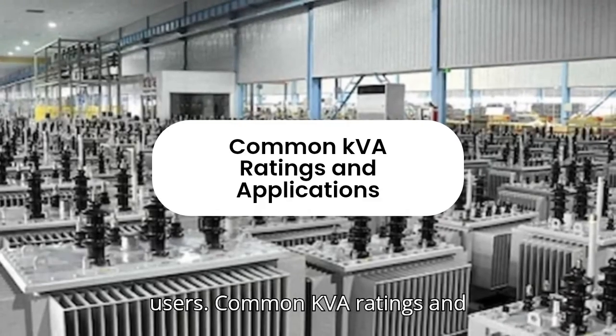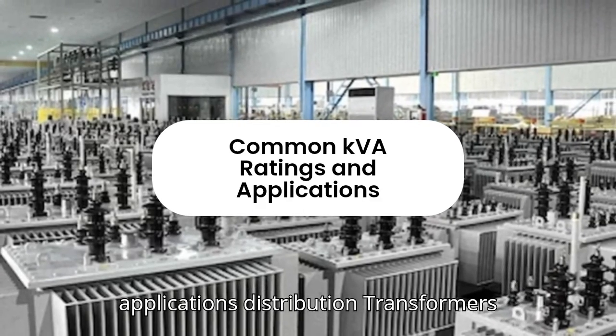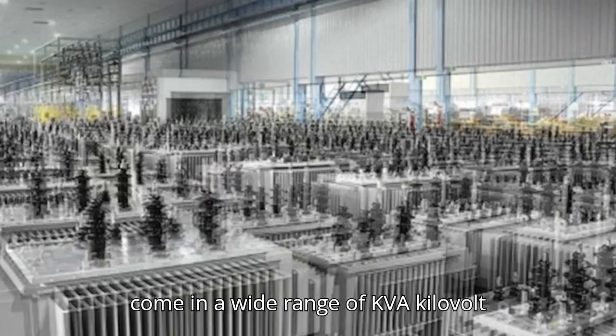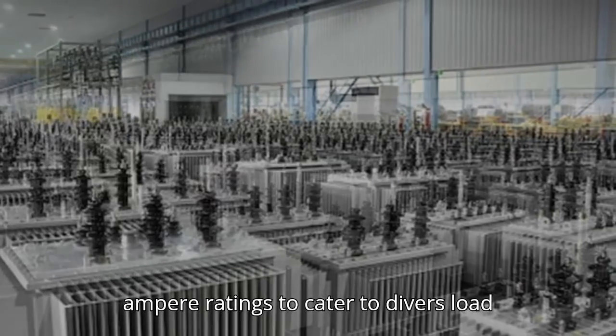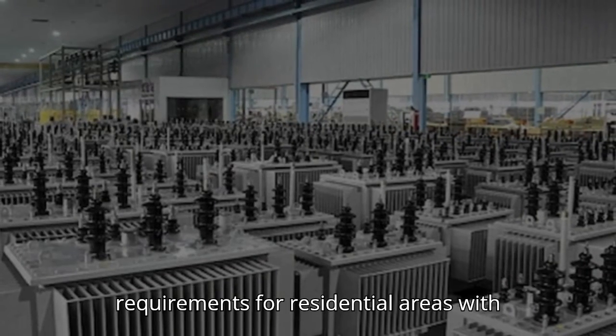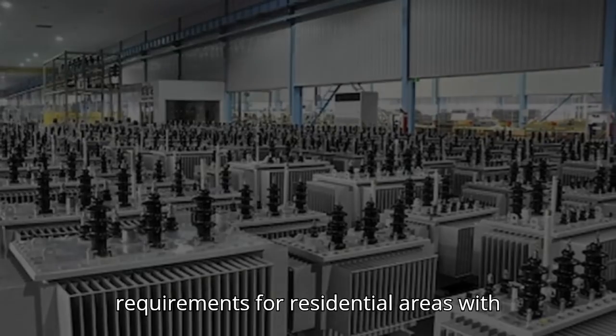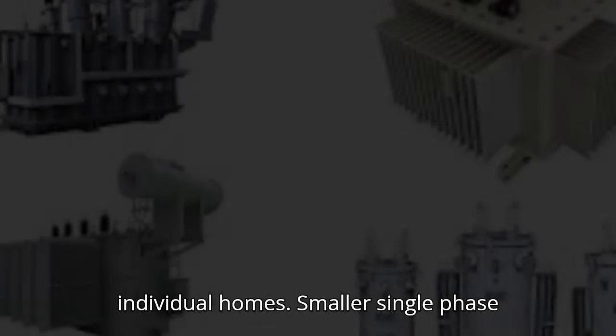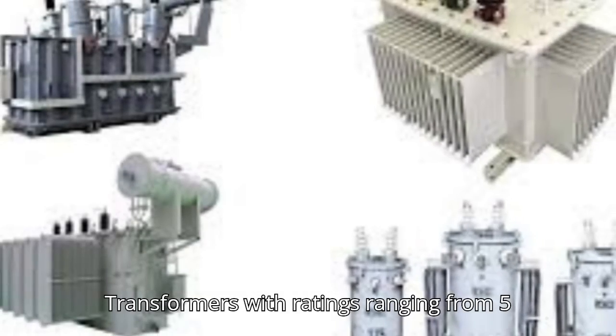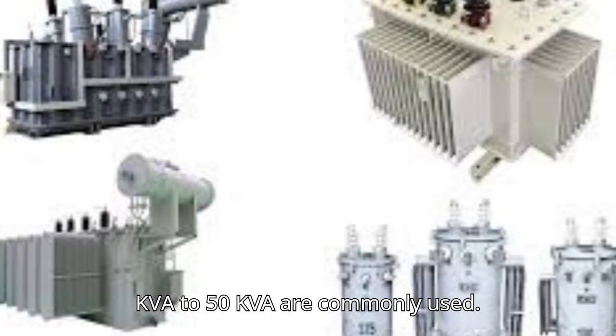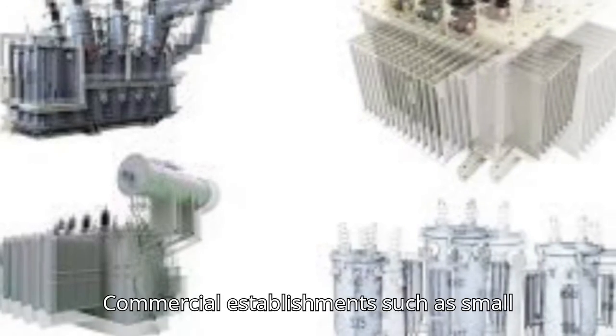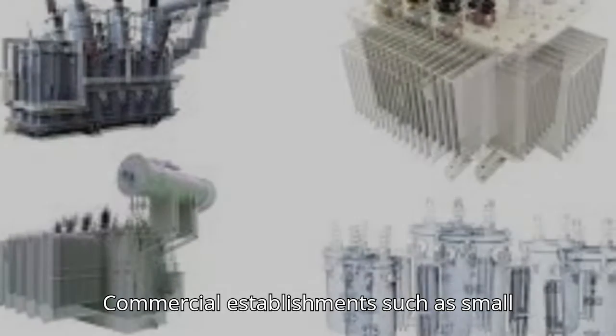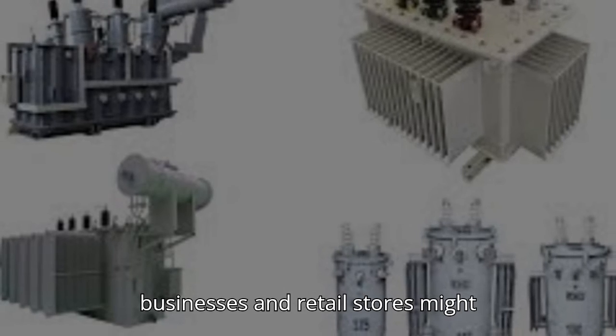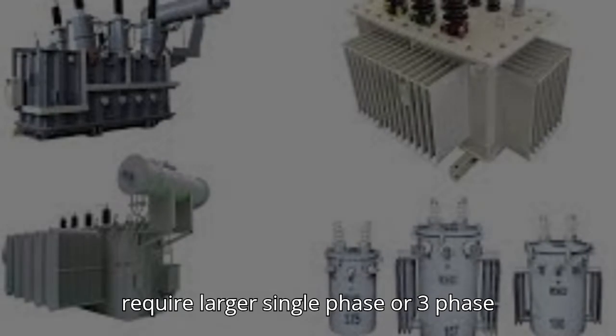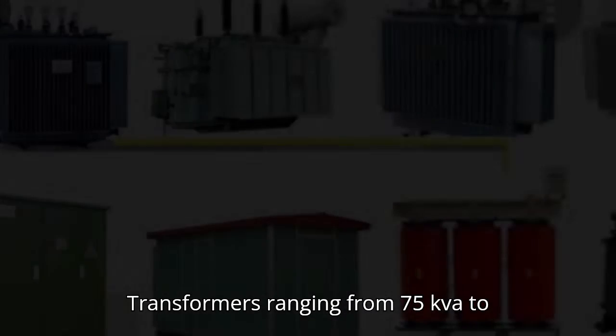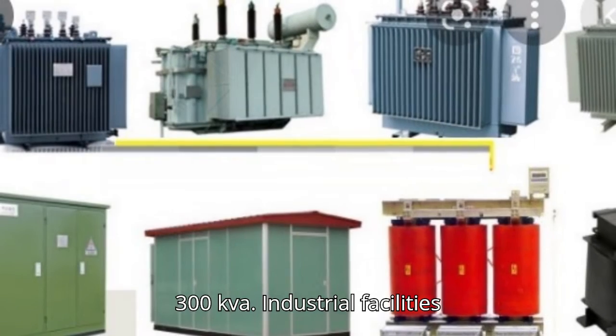Common kVA ratings and applications. Distribution transformers come in a wide range of kVA, kilovolt-ampere, ratings to cater to diverse load requirements. For residential areas with individual homes, smaller single-phase transformers with ratings ranging from 5 kVA to 50 kVA are commonly used. Commercial establishments, such as small businesses and retail stores, might require larger single-phase or three-phase transformers ranging from 75 kVA to 300 kVA.